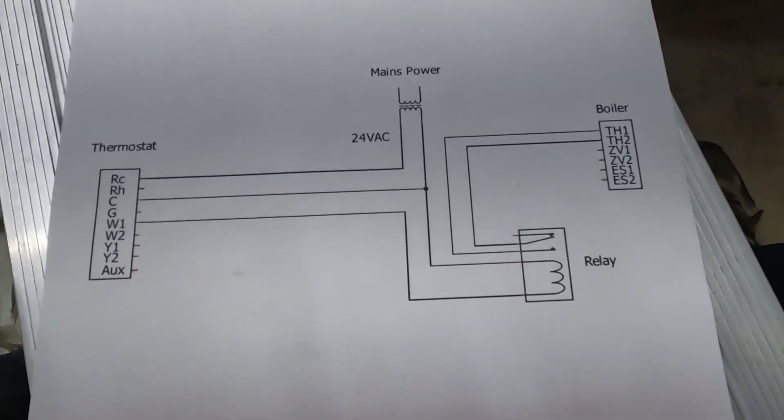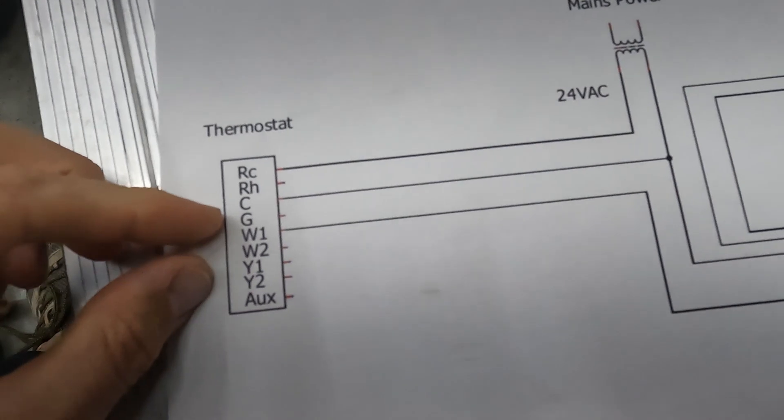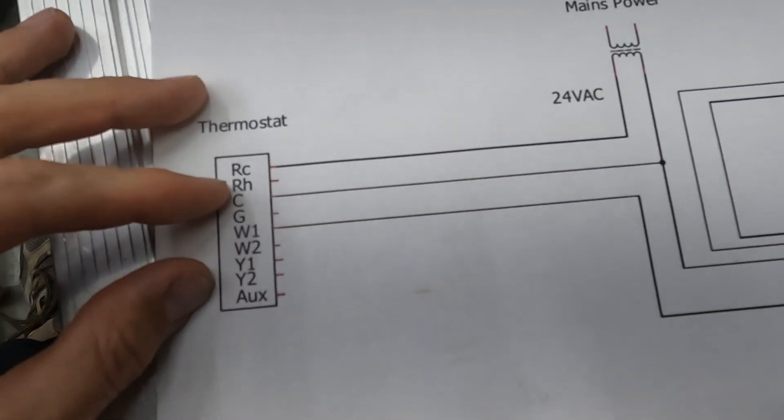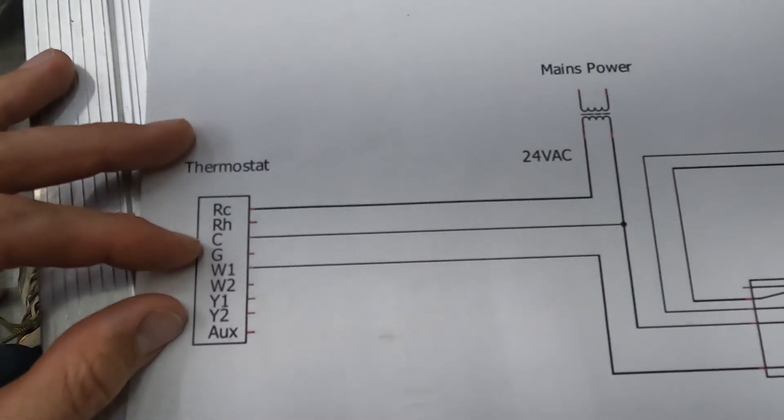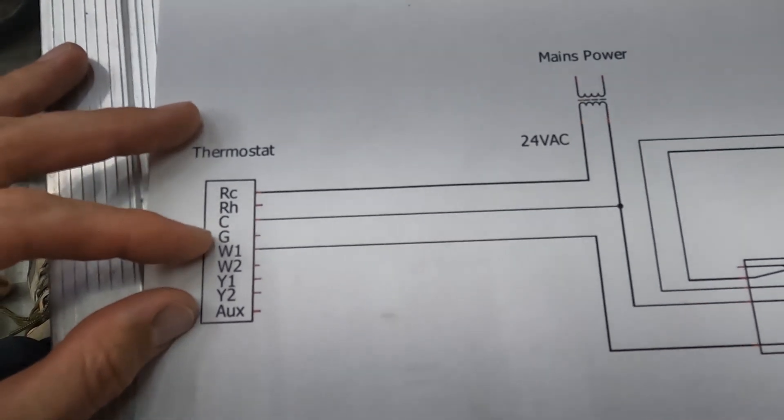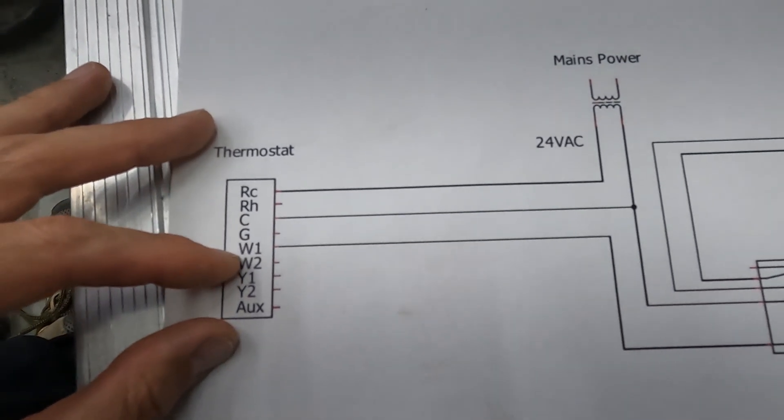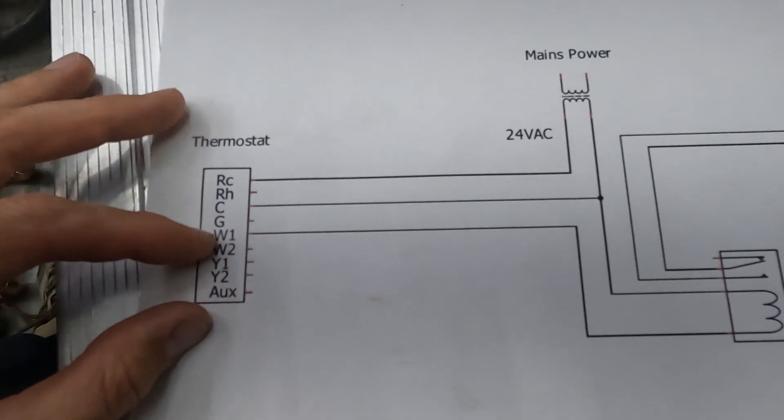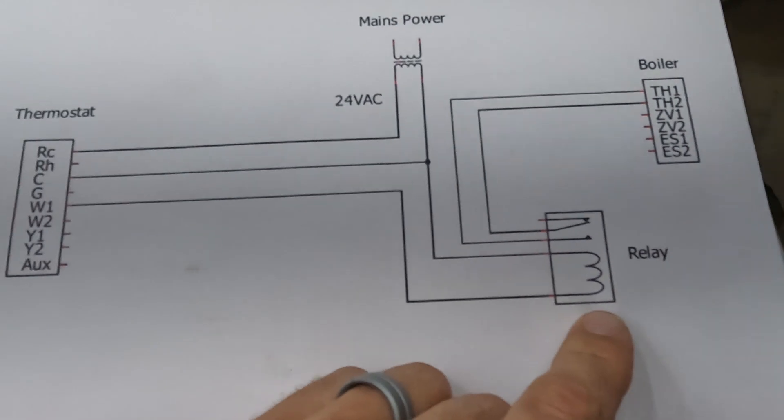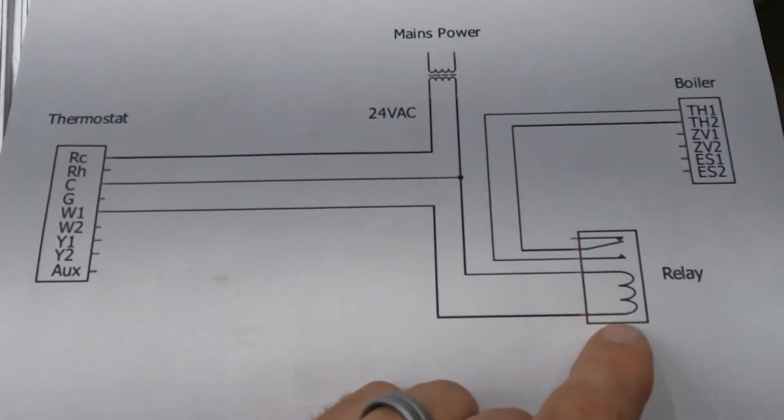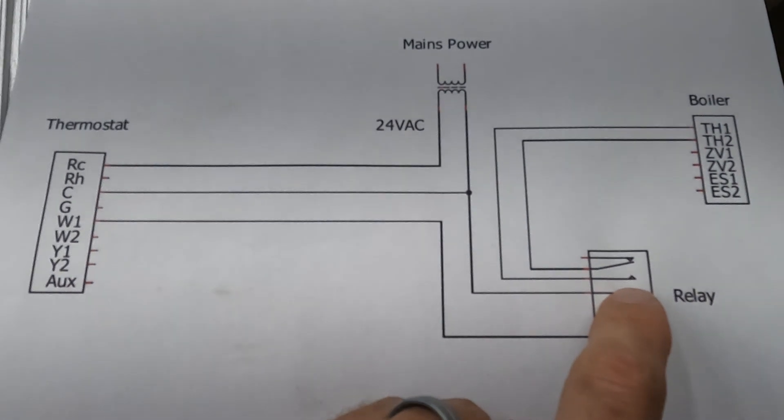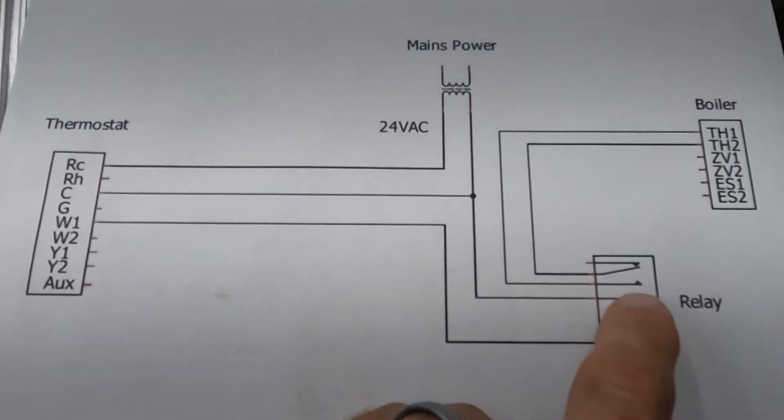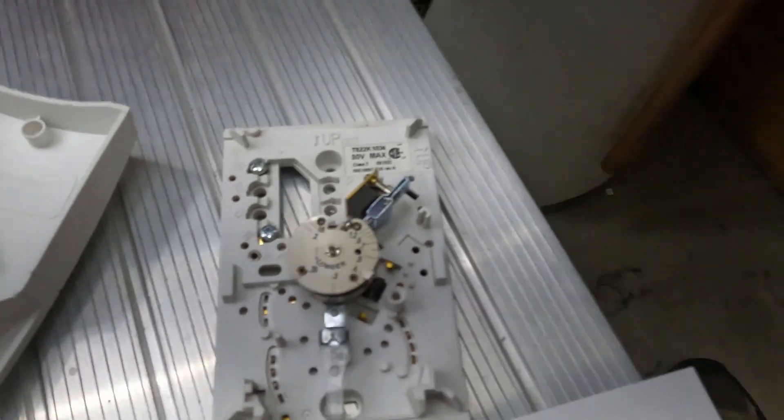But if you want to have an Ecobee, then you're going to need to power the Ecobee somehow. How this works is the RC and the C are powered constantly to give the Ecobee power. Then when you call for heat on the Ecobee, it energizes the W1, and that comes down here to the relay. That energizes this coil, which flips this little switch here, and that is just emulating the switch that you used to have with this guy.